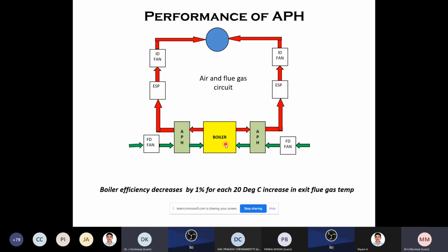The boiler efficiency will also reduce. For a 20-degree increase in the exit temperature we are measuring here, 1% of boiler efficiency will be lost. This is an established fact. So you have to see the performance of the air preheater, how it is performing inside. Is it clear? Yes, sir. Okay.